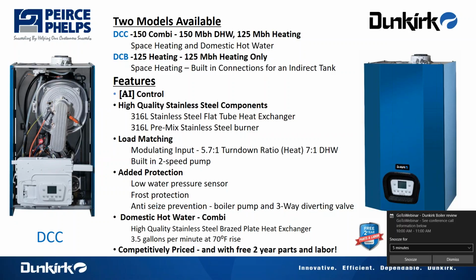On the domestic hot water combi side, a braze plate heat exchanger will be producing 3.5 gallons per minute at a 70-degree rise, which is comparable and the standard that we use in the industry. So again, it's something that is application sensitive. We're not going to put this boiler in a 5-bath home with 4 daughters and environment showers and things like that. It is an application. Probably think a single-family or multi-family application with individually metered, with 2 baths, laundry, and a kitchen sink.